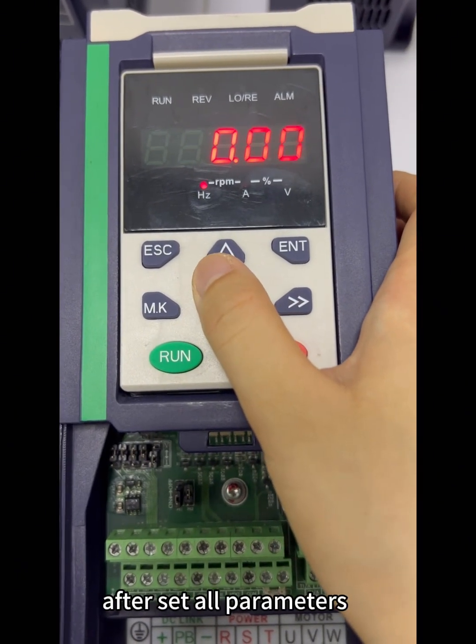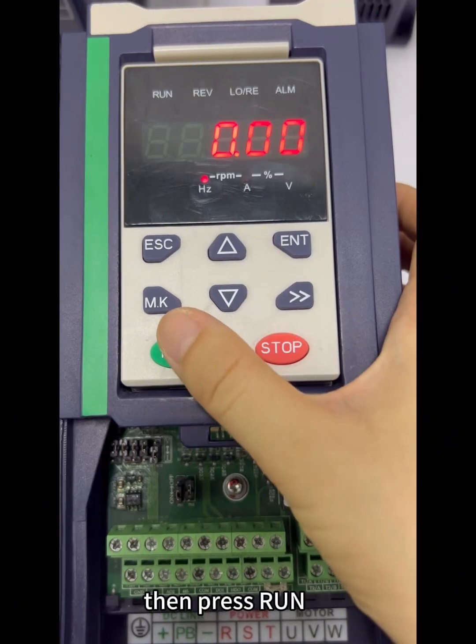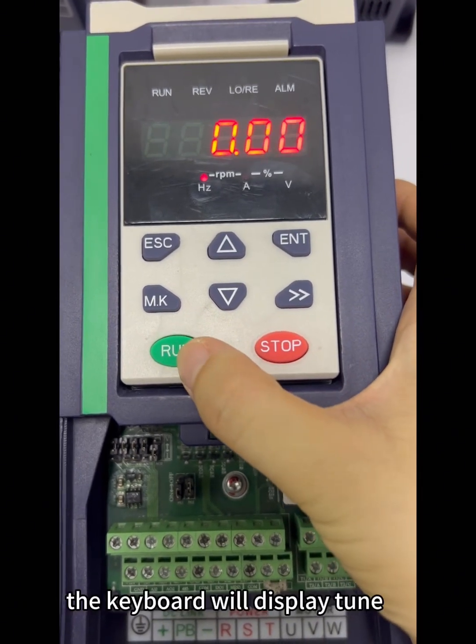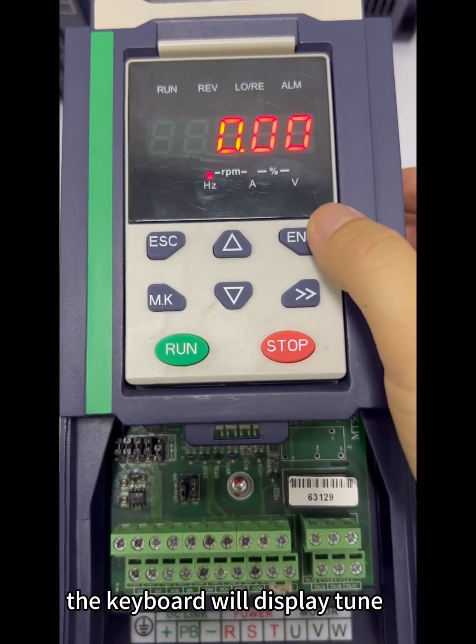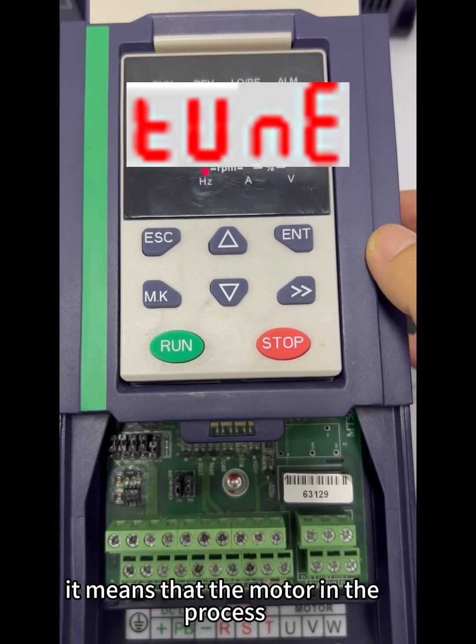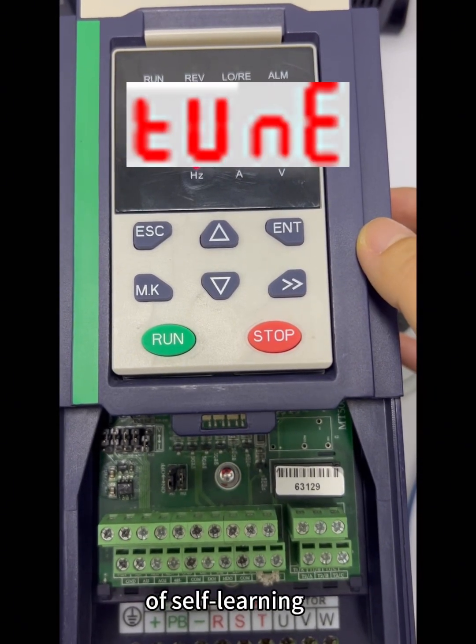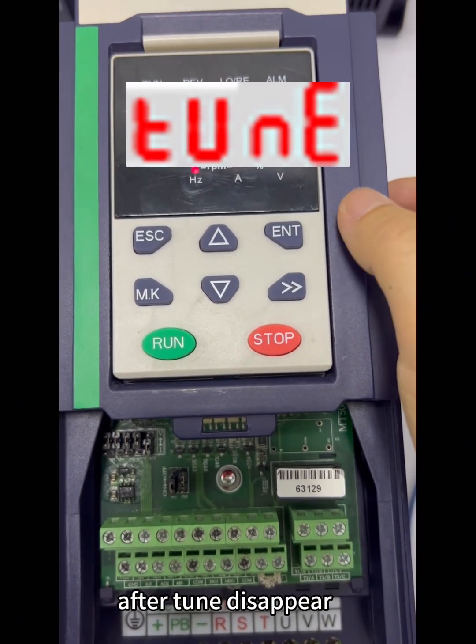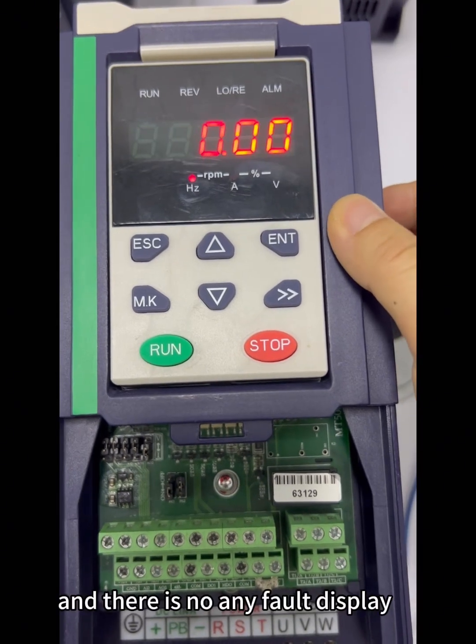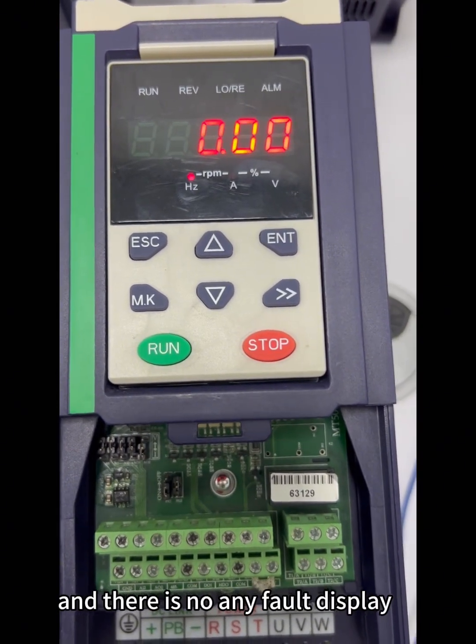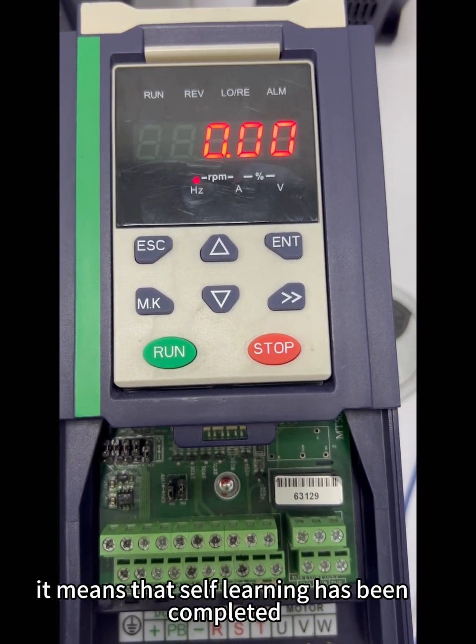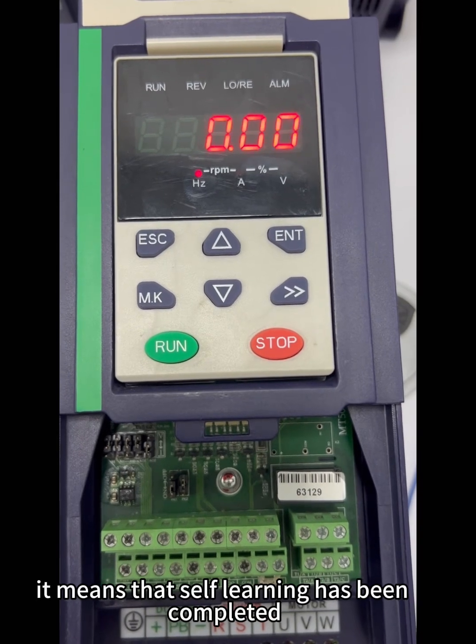After set all parameters, then press Run. The keyboard will display tune. It means that the motor is in the process of self-learning. After tune disappears and there is no any fault display, it means that self-learning has been completed successfully.